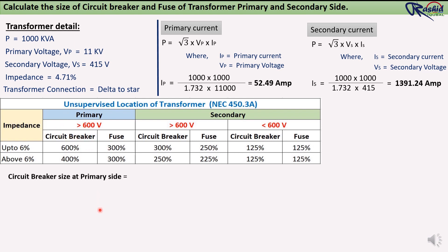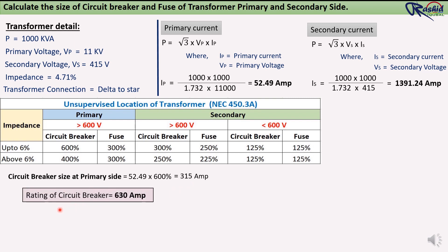Circuit breaker size at primary side = primary current 52.49 × 600% = 315 ampere. Since a 315 ampere VCB (vacuum circuit breaker) is not available in the market, we will select the next bigger size, which is 630 ampere. This 630 ampere VCB is available in the market, so we will use this size.